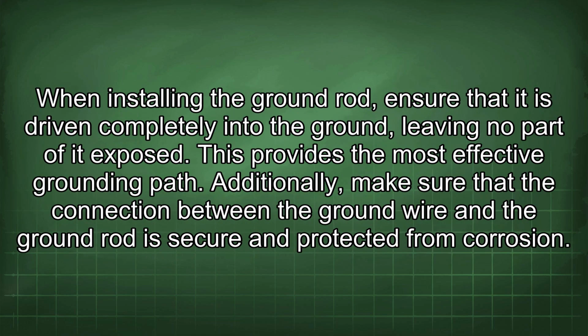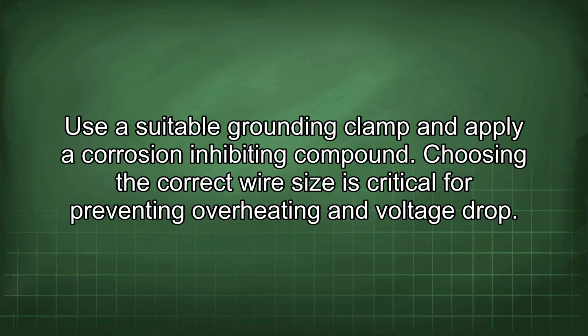When installing the ground rod, ensure that it is driven completely into the ground, leaving no part of it exposed. This provides the most effective grounding path. Additionally, make sure that the connection between the ground wire and the ground rod is secure and protected from corrosion. Use a suitable grounding clamp and apply a corrosion-inhibiting compound.